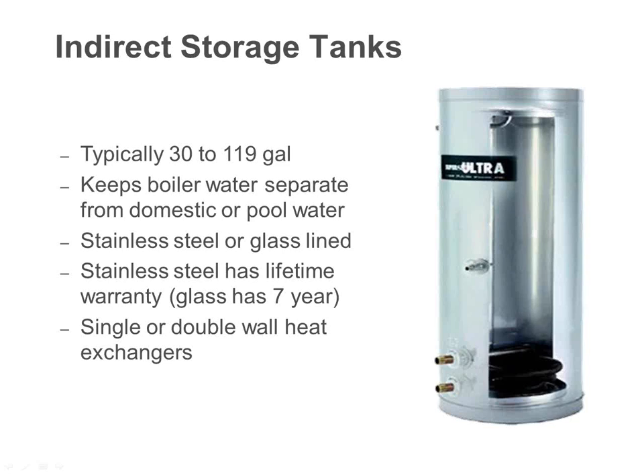So a very simple way to do it is to go to an indirect storage tank. This is nothing more than another zone off your boiler, very small. Normally when we're doing a lot of these churches, I'll take a 50 or 75 gallon water heater and knock it down to a 45. Just because I've got to remember, I've got a boiler over here that might be 500,000 BTUs dumping into that little copper nickel heat exchanger on the bottom, transferring a ton of heat into that tank to make up the water. This gets rid of the whole flue issue.